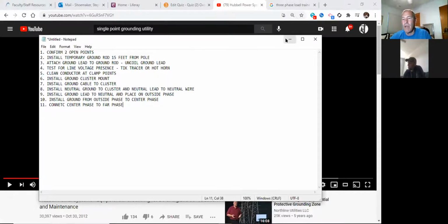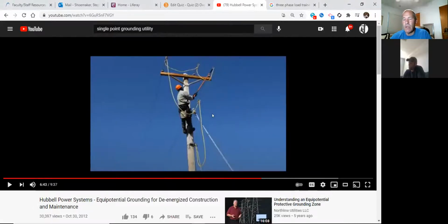Okay, before I start the video back, and you'll see the difference here. When he initially installed the ground cluster, how far away from the neutral was it? What did we say? About 2 feet. He's readjusted this, and you can tell 2 feet would probably put it right around where his kneecaps are. He's readjusted it further down the pole, and I'll tell you the reason why. Whenever you're working in this zone, the zone of grounding, the cluster bar has to be below your feet. It's a requirement in the grounding process, which he has well below his feet right here.